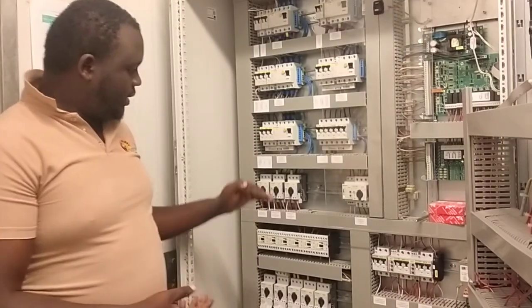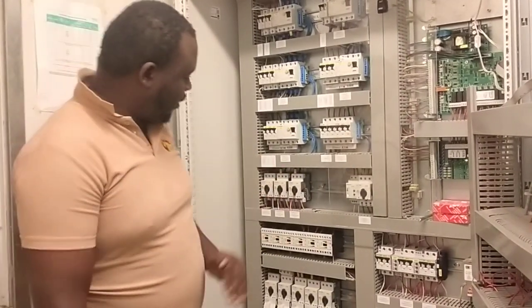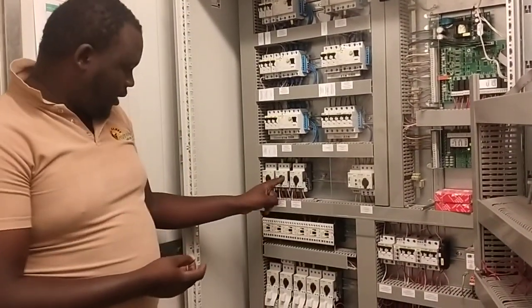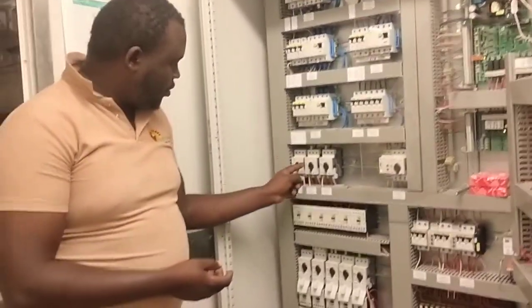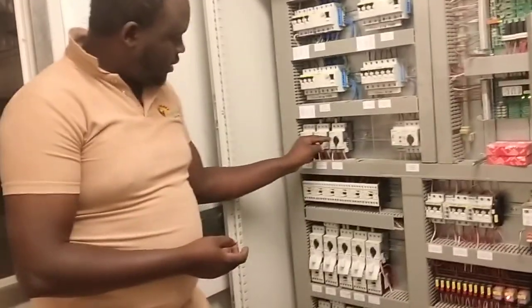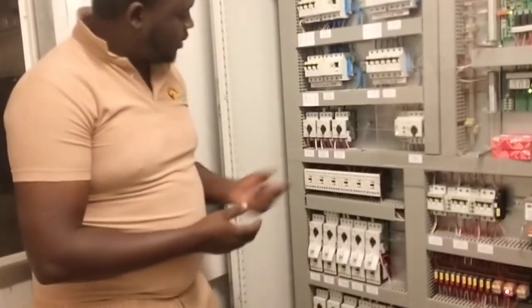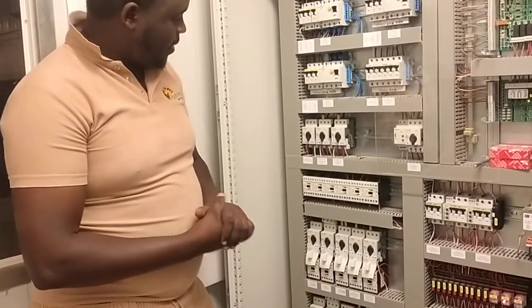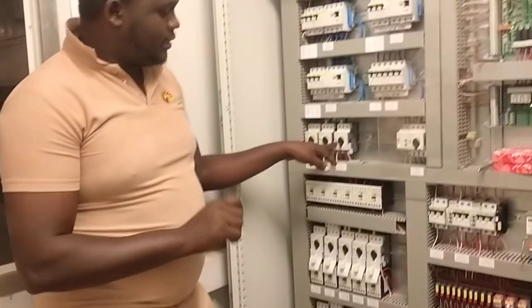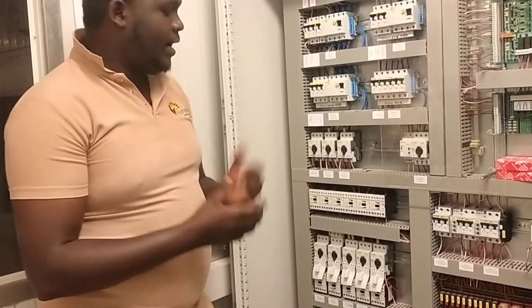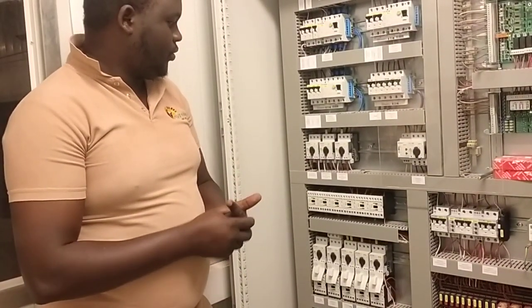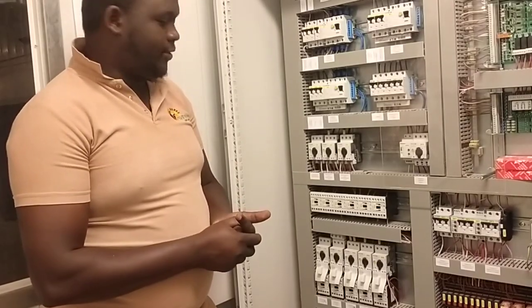So let us go back to the overload protection scheme. As you can see, we have a yellow part in our MCC, in our overload protection scheme. This gives us the allowance to set the current capability of our motors, what we want the motors to operate from.